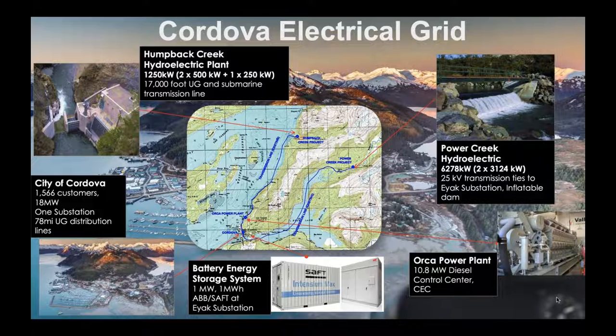In the upper left and upper right-hand corners, you see our two run-of-the-river hydroelectric projects. They're a wonderful resource, providing 70% of our community's energy—pretty much 100% in the summer. But in the winter, as the rivers freeze up and we run out of water, we have to supplement with diesel. When we're 100% hydro, we used to balance our grid by operating deflectors, deflecting about 750 kilowatts of hydro capacity. That was extremely expensive and a waste of renewable energy, so we evaluated several options—next slide, please.